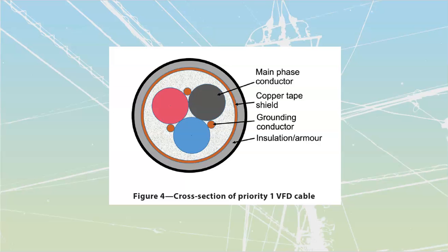So we found that the ground system was going to be very critical, and that sheathing or wrapping was very critical. You'd stick these things inside a conduit and the problems would disappear, because the conduit acts like a Faraday cage. But conduit's not practical everywhere, so you'd look for something else you could run them in. Teck cable became very popular for a while.